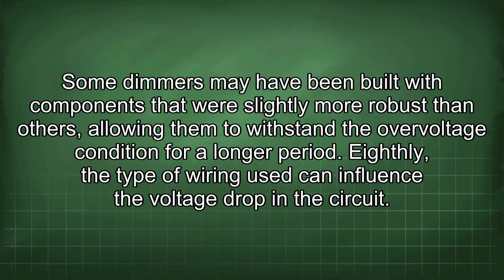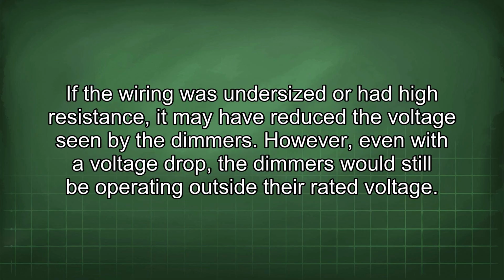Eighthly, the type of wiring used can influence the voltage drop in the circuit. If the wiring was undersized or had high resistance, it may have reduced the voltage seen by the dimmers. However, even with a voltage drop, the dimmers would still be operating outside their rated voltage.